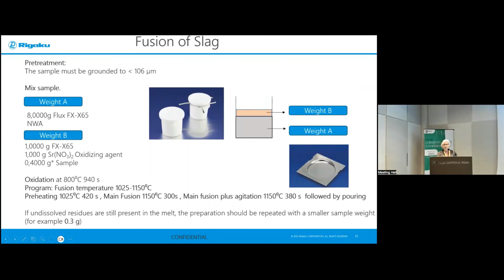So here you can see the example of how we would do a pre-treatment of slag. Why do we need to pre-treat the slag? So slag has the nature that it could be existing in a glassy form or in not an oxidic form, but more a metallic form. So if we directly fuse the slag with platinum, so here you can see an example of a platinum mold, you will then suffer from damaging your platinum because it forms a eutectic mixture with the platinum and it can degrade the platinum, causing pits and so on. So therefore we have to introduce an oxidizing agent. So the oxidizing agent in this case is called strontium nitrate. So we pre-treat the sample in this way, but we use now not platinum crucibles, but we use these alumina crucibles that can be subjected to the very high temperatures of around about 800 degrees.